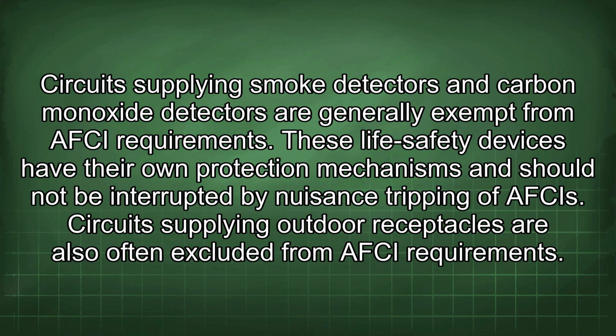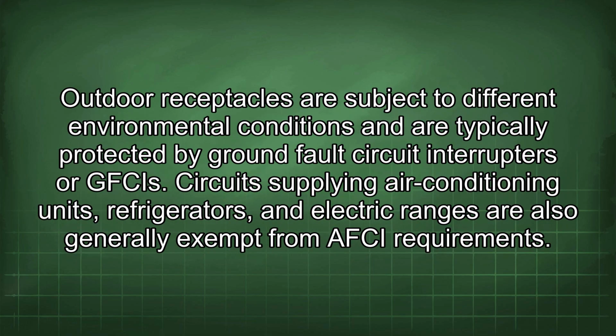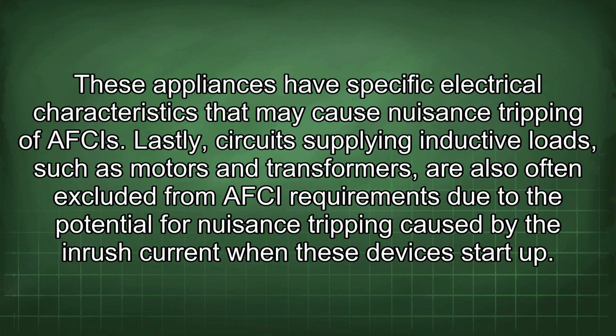Circuits supplying outdoor receptacles are also often excluded from AFCI requirements. Outdoor receptacles are subject to different environmental conditions and are typically protected by ground fault circuit interrupters or GFCIs. Circuits supplying air conditioning units, refrigerators, and electric ranges are also generally exempt from AFCI requirements. These appliances have specific electrical characteristics that may cause nuisance tripping of AFCIs. Lastly, circuits supplying inductive loads, such as motors and transformers, are also often excluded from AFCI requirements due to the potential for nuisance tripping caused by the inrush current when these devices start up.